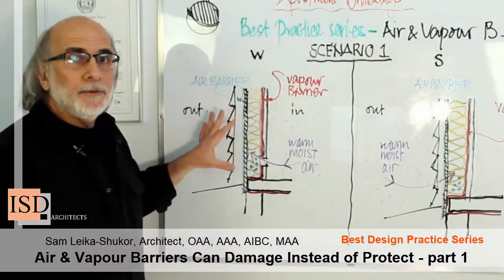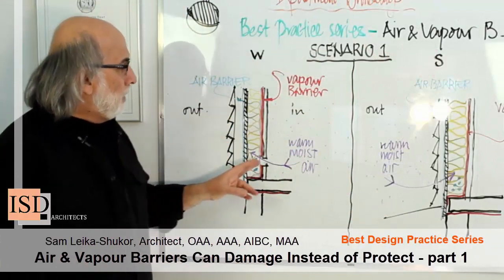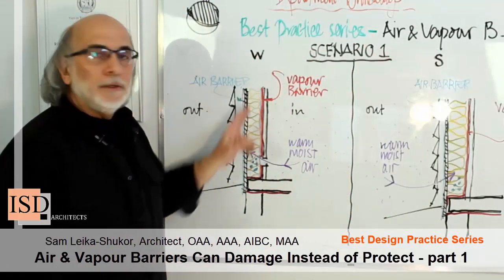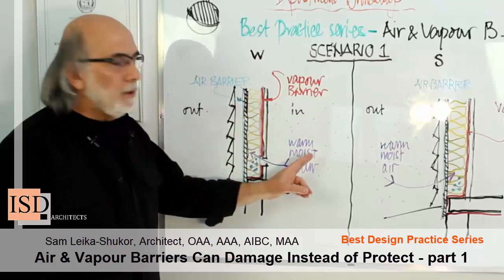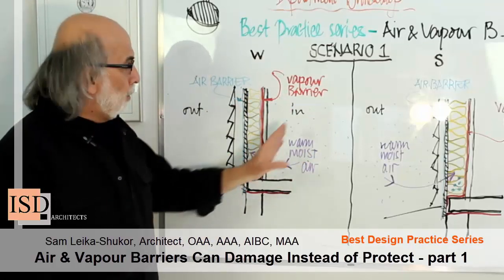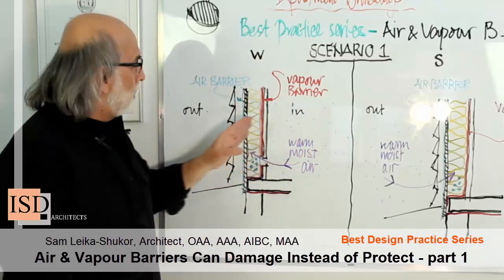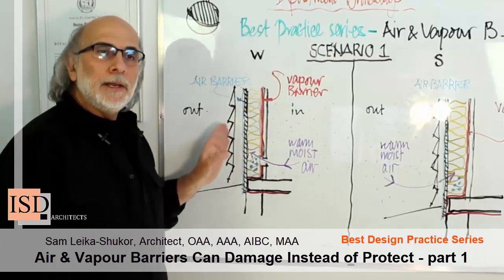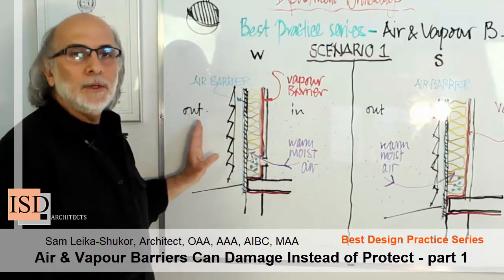What's the problem with that in the wintertime is that this vapor barrier cannot prevent air leakage from the warm to the colder layers of the wall, because this is winter, as you remember.